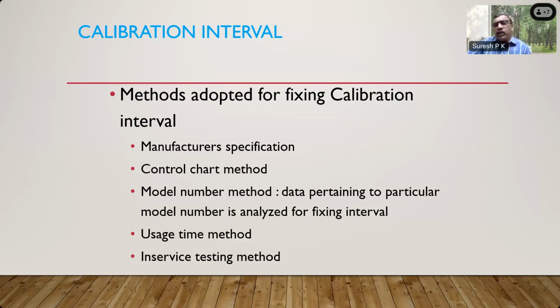Now there are always questions asking how the methods are adopted for fixing the calibration interval. This is actually legal metrology. As per legal metrology rules, it is 1 year. Please correct me if I'm wrong, sir. It is 1 year, but as far as you are concerned, if you are using a standard for calibration, like a flow meter used as a master meter, which is very rarely used, then you can calibrate that master meter once in 2 years or once in 3 years. But depending on the accuracy criticality, you may go in for once in 6 months also, because even for 6 months you are not able to sustain if there is a loss.